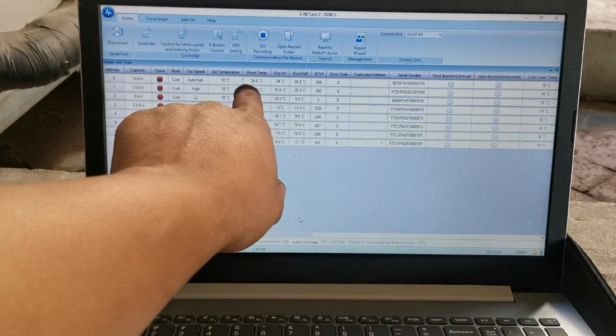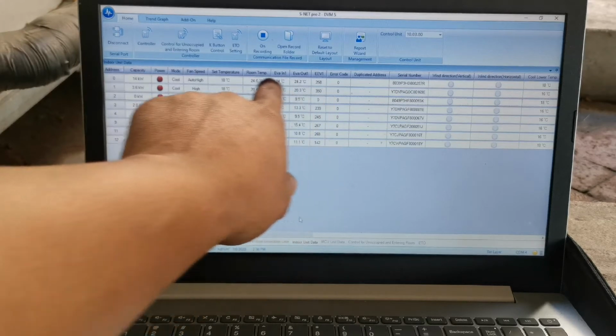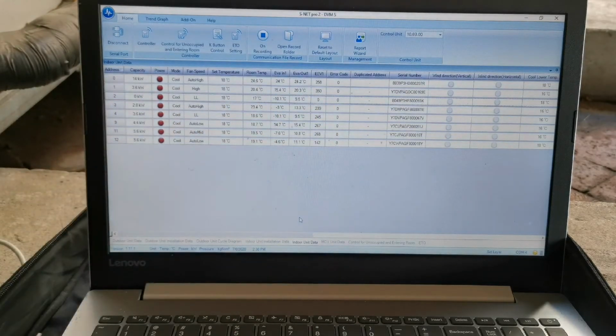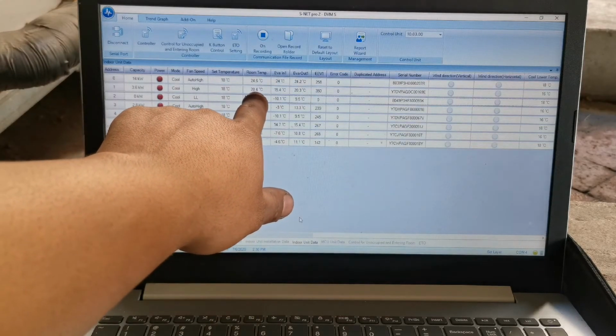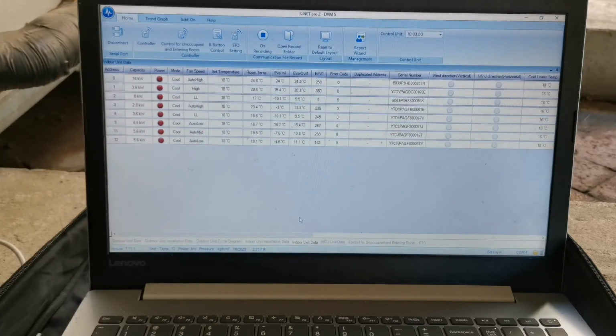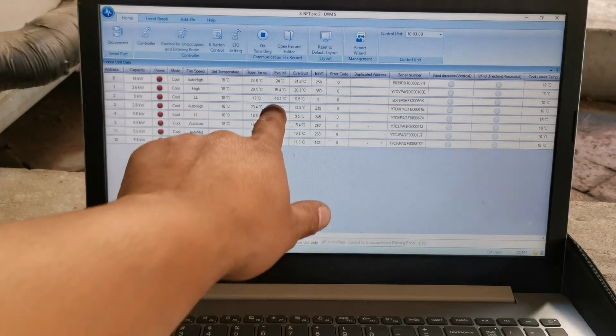Interesting. We basically equalized room temp, evaporator in and evaporator out, yet the expansion valve made about 258 steps. Our room temperature on the second unit hasn't changed much. It's still been on 20.4, although we have a 4 degree difference on our evaporator. This is crazy right here.